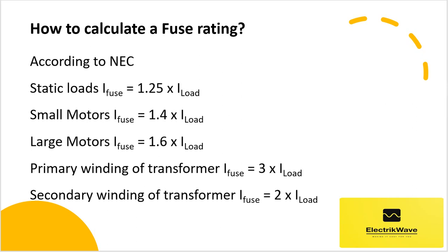According to NEC, you may calculate fuse rating as shown here for various loads: for static load, fuse rating would be 1.25 times load current; for small motor, 1.4 times load current; for large motor, 1.6 times load current; for the primary winding of a transformer, 3 times load current; and for the secondary winding of a transformer, 2 times load current.